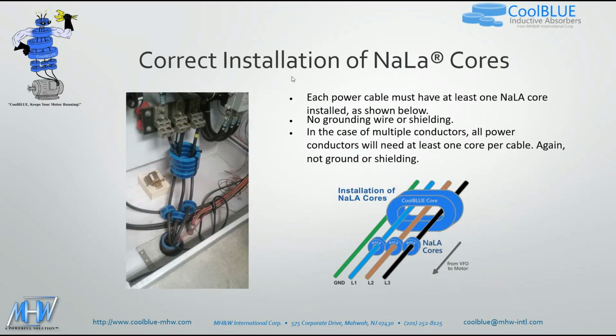The correct installation of NALA cores. Again, as I mentioned earlier, a NALA is going to be over each individual line, as shown here in the picture. So in our 75 horsepower, 150-foot application, it was 1 core per line. So you put one on L1, one on L2, and one on L3. Again, no grounding wire, hanging wire, or any type of conductive wire should go through there other than your L1, L2, L3 leads. Again, and no type of shielding can go through.